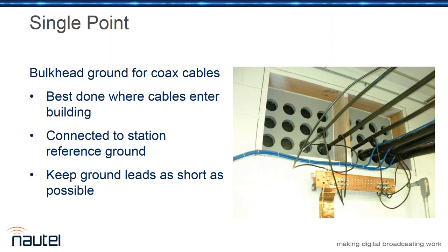Is it advisable to connect the protection rod directly to the grounding system, or better to have a separate rod ground? This depends on whether we're talking AC protection versus lightning protection, like the power company's AC entrance ground. It will depend somewhat on your local code. Here in North America, the NEC was rewritten about 10 years ago to specify that the AC entrance ground must be tied to facility ground, so your lightning protection ground must be tied to your AC ground in this part of the world. Local codes will always be more applicable, so I can't answer for every part of the world, but if you're in the US or Canada, they must be tied together.